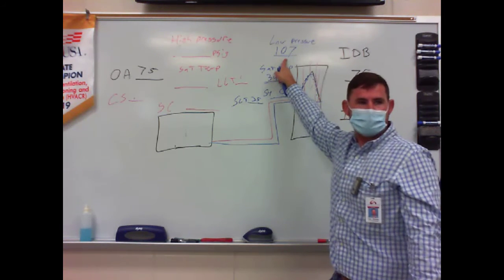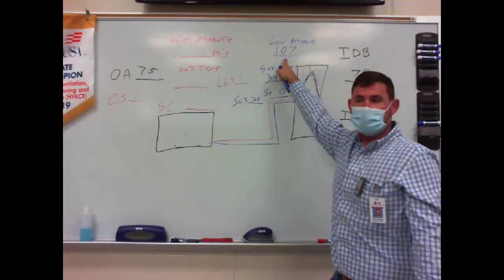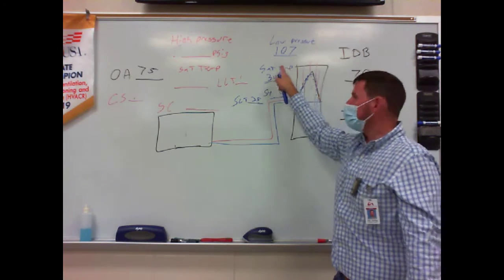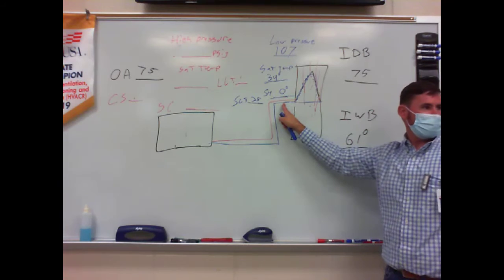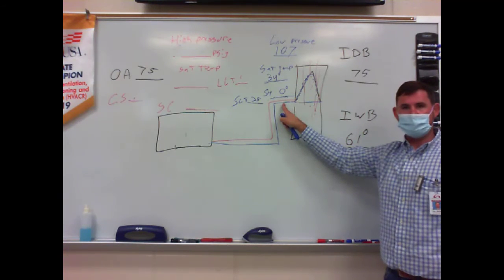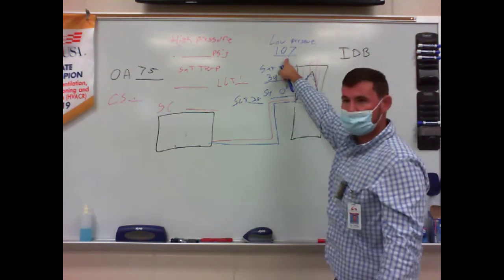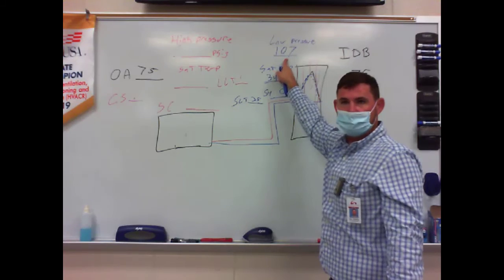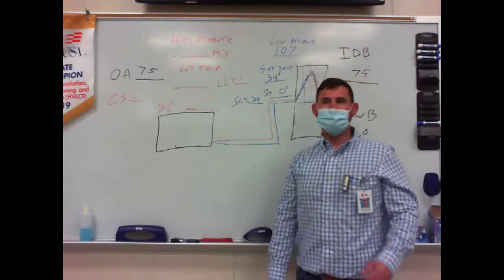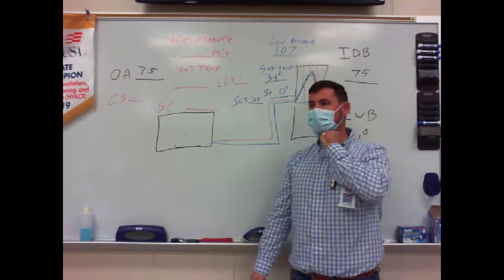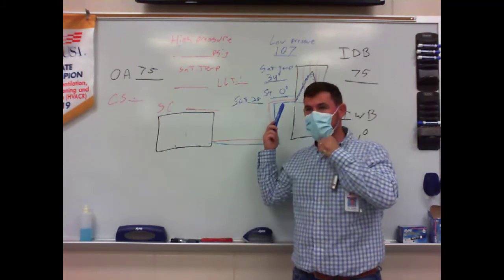How's he going to get that pressure up? He's going to dump more refrigerant in, right? But what's happening? I'm already flooded. I'm already sending liquid back to my compressor. What's going to happen when Bubba dumps a bunch more refrigerant in on this? We're slugging that compressor now. That's exactly right, and we're going to damage it. Why? Because Bubba don't understand how this system works.